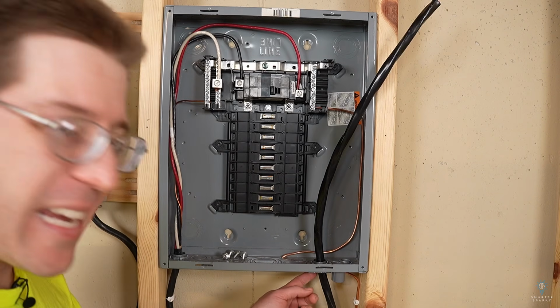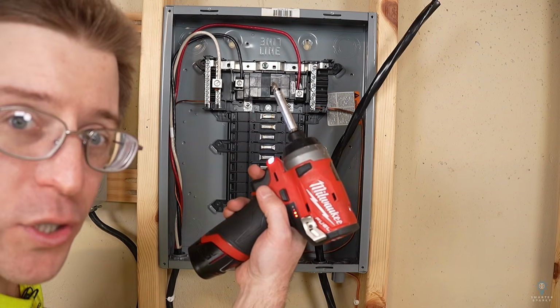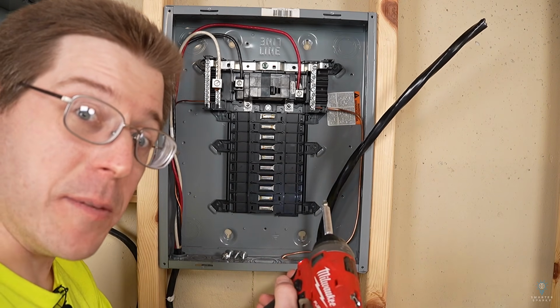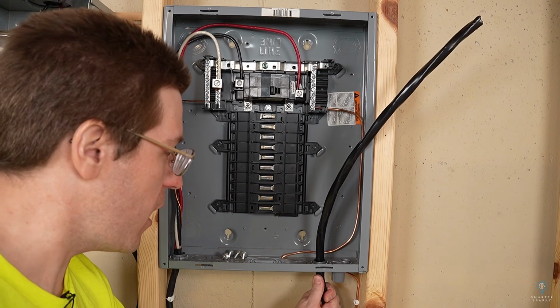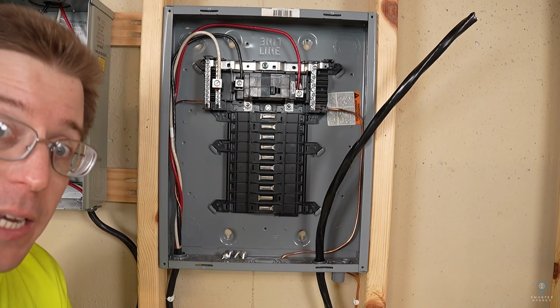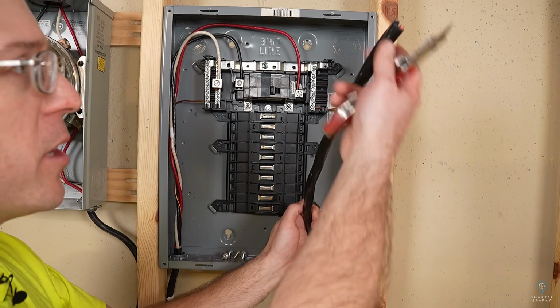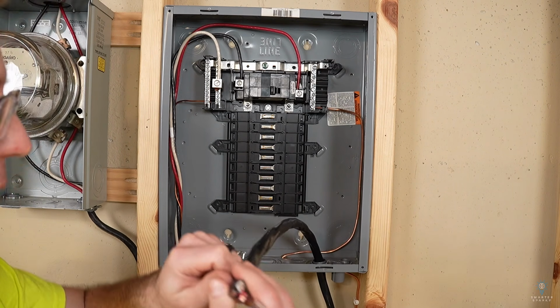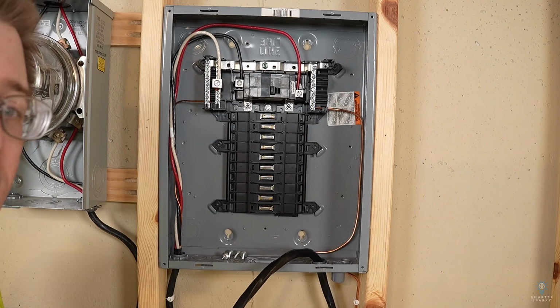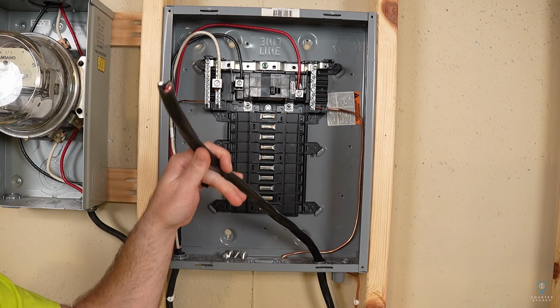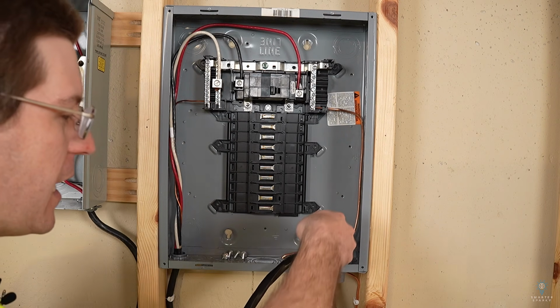I'm going to go ahead and tighten the clamp on the bottom here. I'm just going to use a drill this time. Again, it doesn't need to be super tight. It just needs to be snug enough that that wire is not going to want to come out of that connector. And just like with the sub panel, I'm going to score the outside of the sheath and then peel it back like a banana. This time I did not score the bottom there, so you guys will be able to see what that's like.